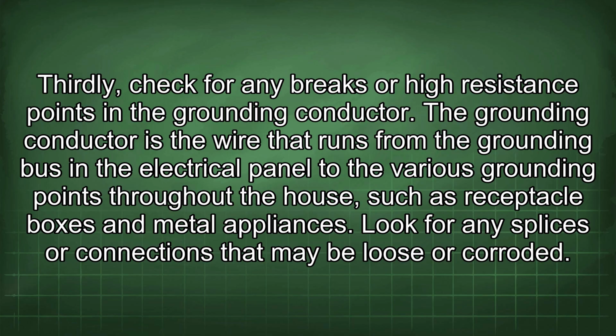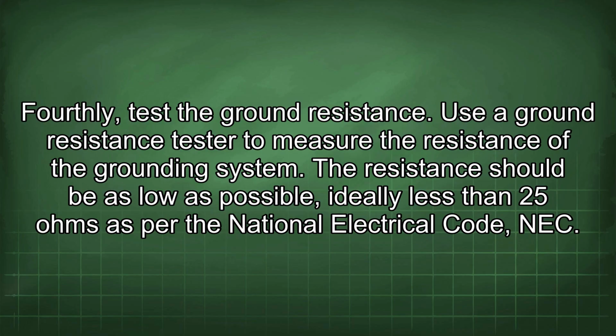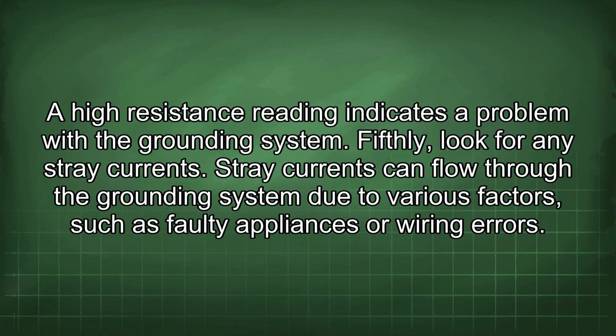Thirdly, check for any breaks or high resistance points in the grounding conductor. The grounding conductor is the wire that runs from the grounding bus in the electrical panel to the various grounding points throughout the house, such as receptacle boxes and metal appliances. Look for any splices or connections that may be loose or corroded. Fourthly, test the ground resistance. Use a ground resistance tester to measure the resistance of the grounding system. The resistance should be as low as possible, ideally less than 25 ohms as per the National Electrical Code (NEC). A high resistance reading indicates a problem with the grounding system.